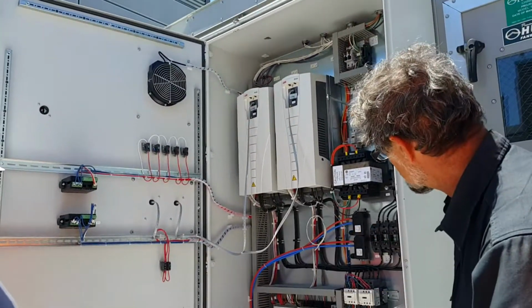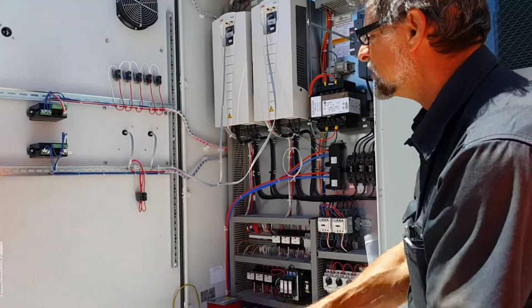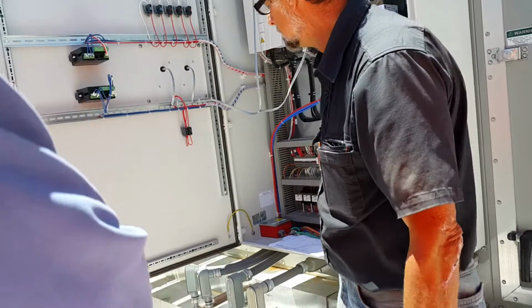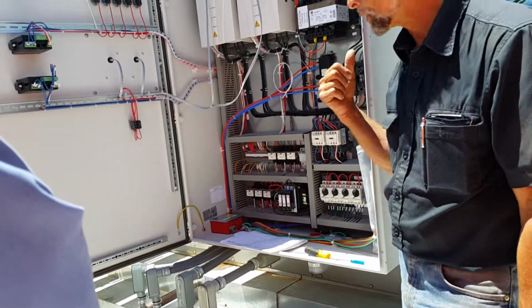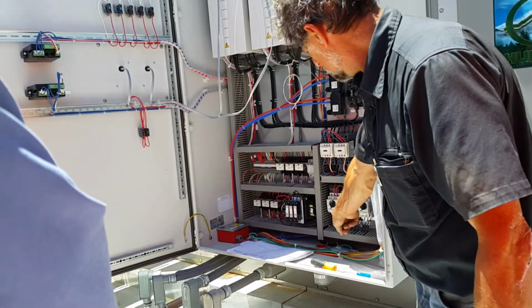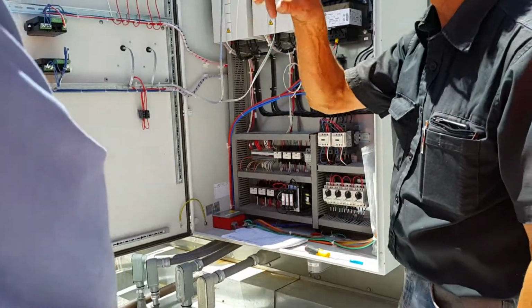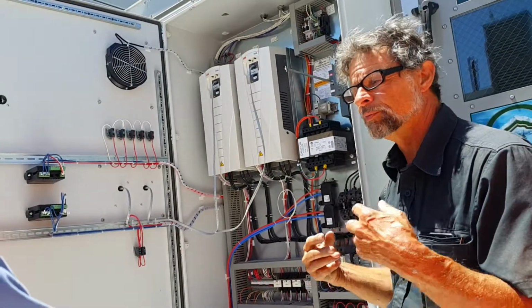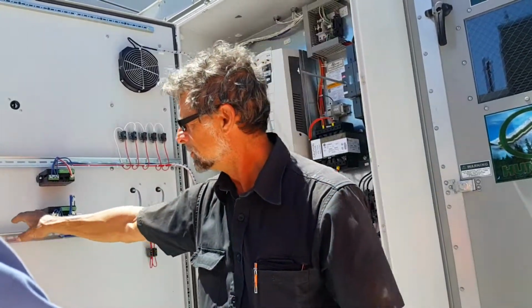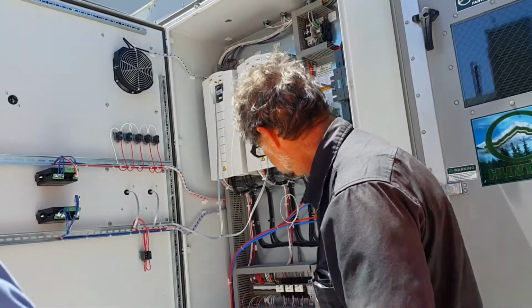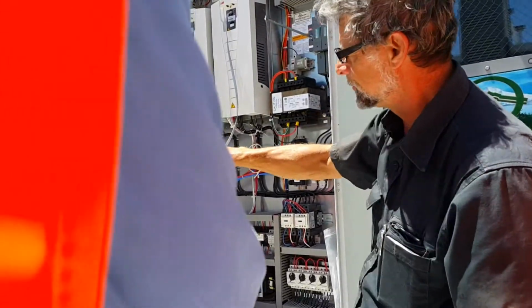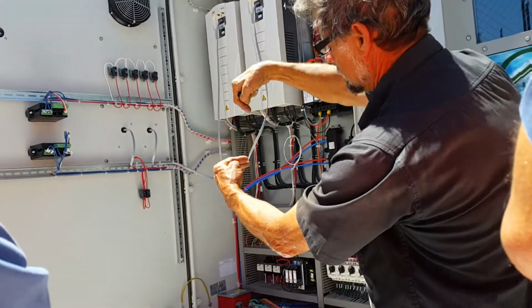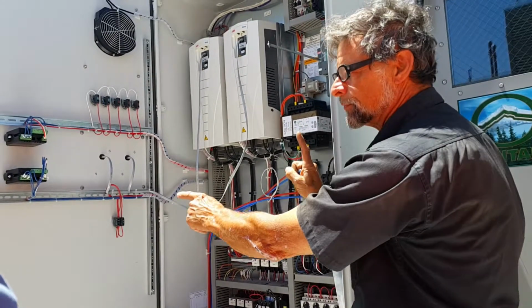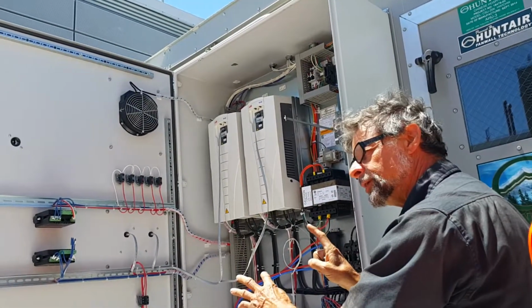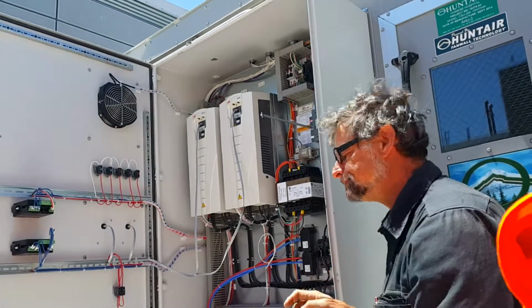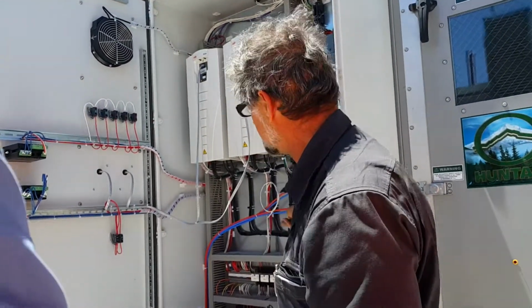And there's a difference in here. The airflow things we didn't talk about over there are here. There's a set of tubes on the inlet cone. Probably one for one set, one for the other set. Over there we had 2, one for each 3 fans, because we had 6 over there. So on the inlet cone itself, it's curved where the air comes in. A little hole here and a little hole up here. They're actually just measuring the difference in pressure between where the air comes in and where it's lowest in the system. That pressure differential is on the transducer here.